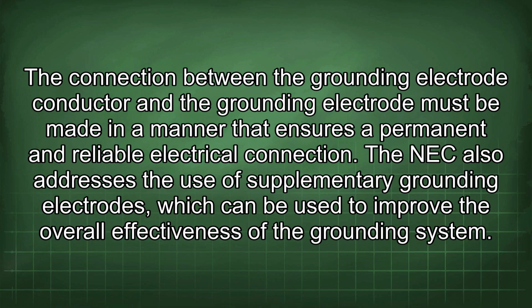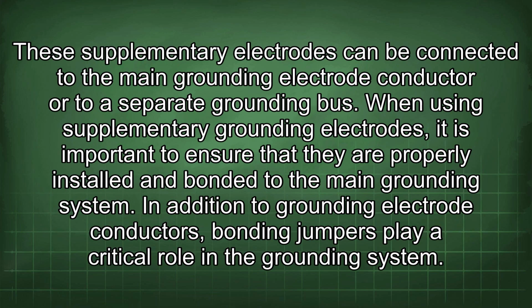The NEC also addresses the use of supplementary grounding electrodes, which can be used to improve the overall effectiveness of the grounding system. These supplementary electrodes can be connected to the main grounding electrode conductor or to a separate grounding bus. When using supplementary grounding electrodes, it is important to ensure that they are properly installed and bonded to the main grounding system. In addition to grounding electrode conductors, bonding jumpers play a critical role in the grounding system.